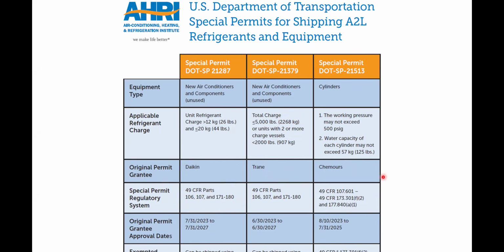If you want to transport cylinders of refrigerant more than 20 pounds, a normal R-454B or R-32 cylinder is only 20 pounds. But if you want to transport more than 20 pounds, specifically 20 to 125 pounds, Chemours has a permit that you can use. So if you can get your hands on a 100-pound cylinder of R-454B, which is a thing, you can buy it that way. I don't know if we have any of them in our inventory yet, but you can buy that. Then you would just use this Chemours permit in order to be able to transport it.